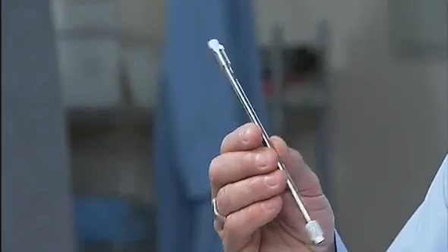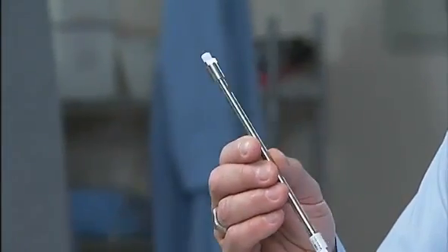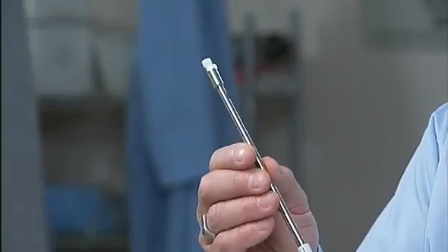The LC column is fully packed with particles. The column is well swept by mobile phase. There are no dead spots or other hiding places for contaminants. Column manufacturers work very hard to ensure that there are no dead volumes in the column. If there were dead volumes, they would contribute to extra column band broadening or give tailing peaks. So, if we flush the column, we should not expect ghost peaks to appear from contamination that had been hiding on the column.